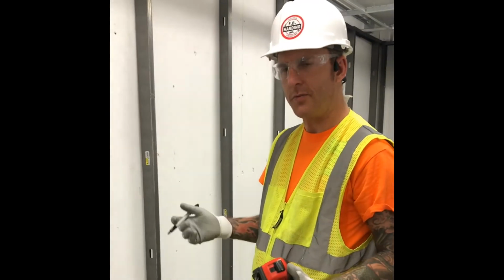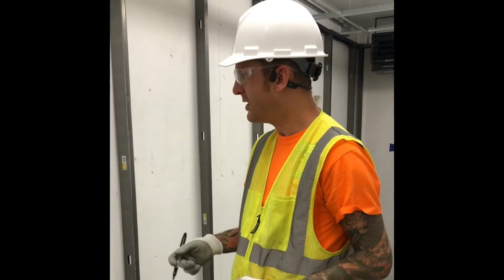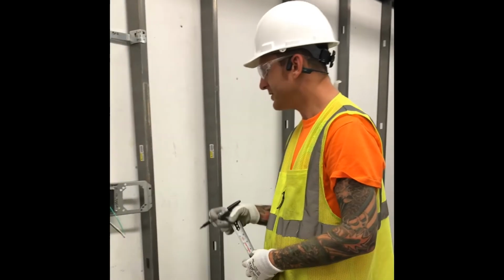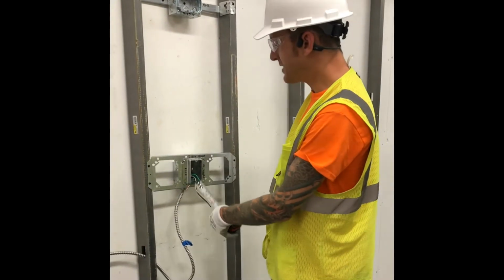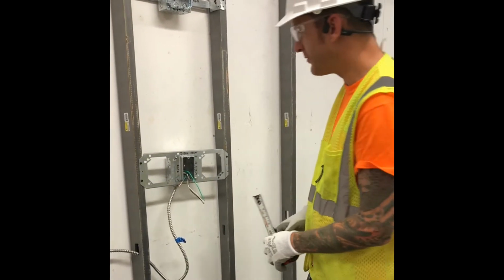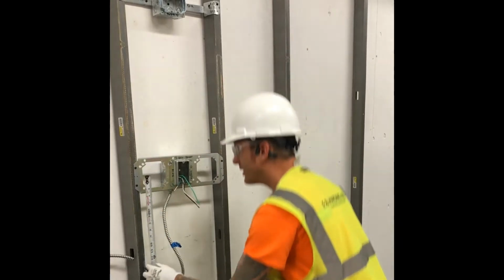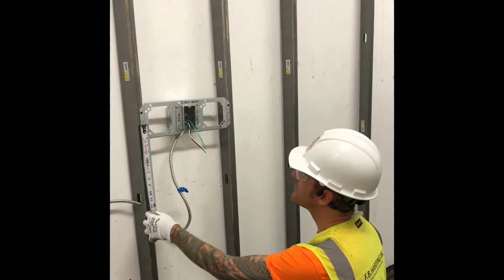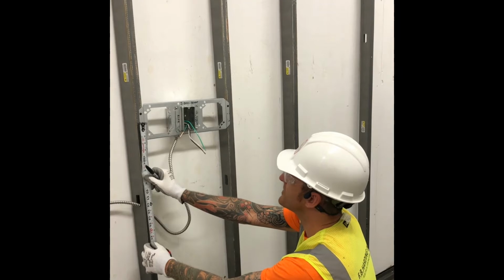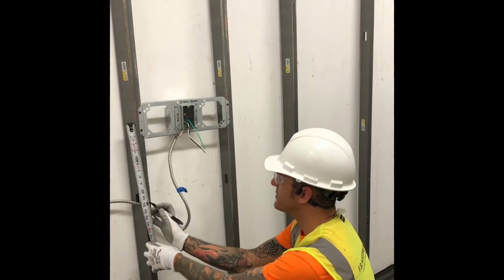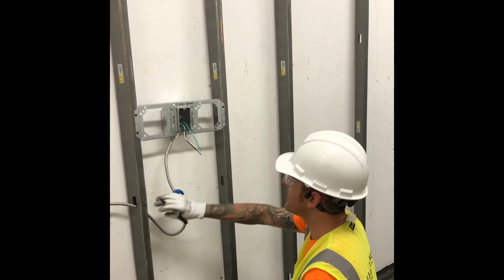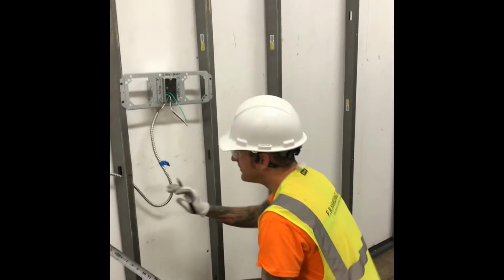Okay, so what we talked about before about necessary supports according to our National Electrical Code and jurisdictional inspections: within any box with MC, it needs to be supported by your listed means of support. From your box, I generally go from the center of the box and make a mark at 12 inches. From any box, it's got to be 12 inches of support.